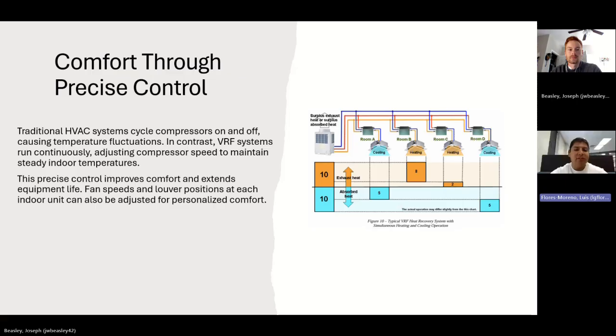Comfort through precise control. Traditional HVAC systems cycle compressors on and off, causing temperature fluctuation. In contrast, VRF systems run continuously, adjusting compressor speed to maintain steady indoor temperatures. This precise control improves comfort and extends equipment life. Fan speeds and louver position at each indoor unit can also be adjusted for personal comfort. Here to the right, we've got Figure 10, which is a typical VRF heat recovery system with simultaneous heating and cooling operation.